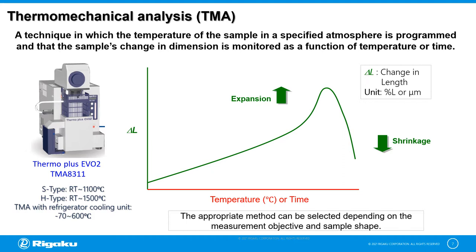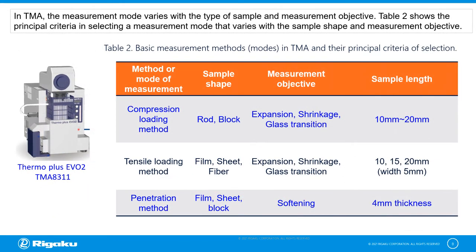With our TMA system, you can measure from room temperature up to 1500 degrees centigrade. In TMA, the measurement mode varies with the type of sample and measurement objective, and the criteria for selecting a measurement mode are shown in this table. The compression loading method is used to measure rod type or block type samples for the detection of expansion, shrinkage, and glass transition of a material ranging from 10 mm to 20 mm in length. In this webinar, we will show you how to measure a sample with a length of less than 10 mm.